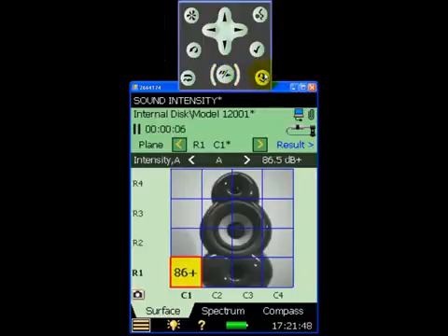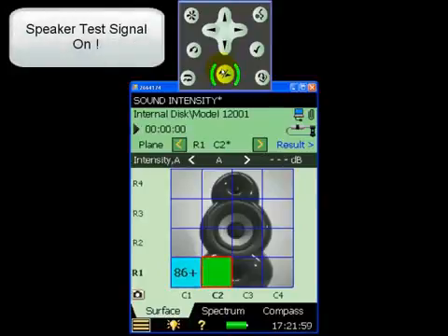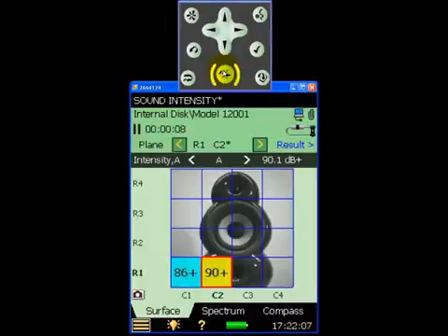The measurement appears to be okay with no overload or warnings, so now we simply store the measurement and move to the next grid position. Again, we appear to have a good measurement. This process is repeated for each of the measurement positions until the grid has a full complement of 16 measurements.